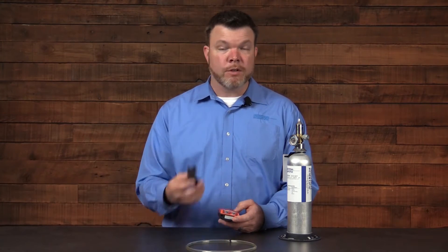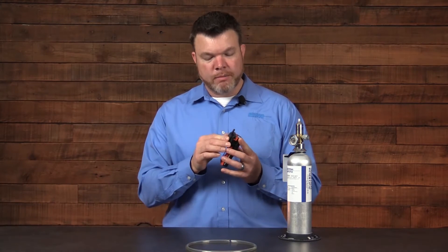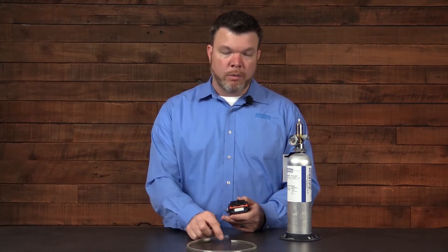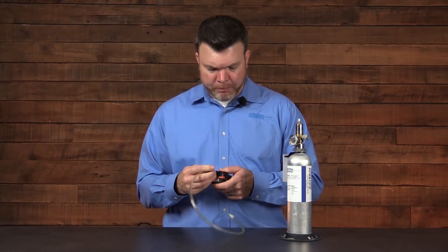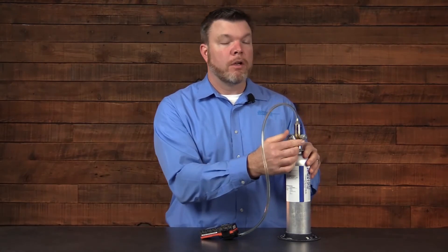Let's go through the apparatus. First I have my calibration cup that would be connected to the front of the instrument. Make sure that it's securely applied to the front here for the sensor areas. We have the tubing, either 1/8 or 3/16ths diameter. The other end of the tubing would be attached to my regulator — standard, half a liter per minute, constant flow.